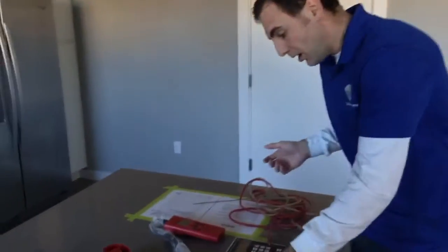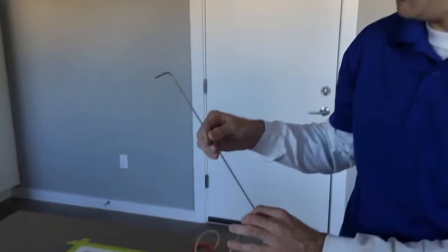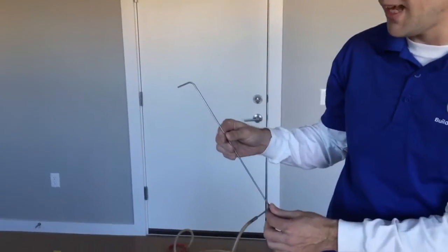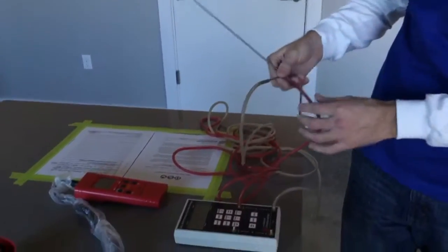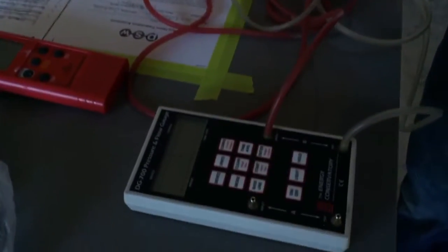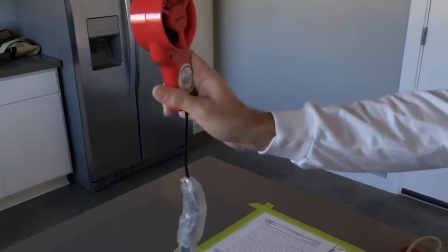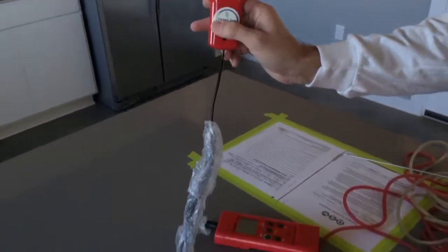So there are several different ways to measure airflow, probably like 7 or 8 or so. Here are a few laid out on the table, aside from the balometer, which I showed you earlier. We've got here a pitot tube that's going to be measuring static pressure as well as velocity pressure. That's why there are two tubes here. Then there's this anemometer here, which you basically point the aperture and then take basically an average reading of the airflow through this fan. Like I said, there are many other ways to measure airflow. It just depends on what your project needs are and what you're doing.